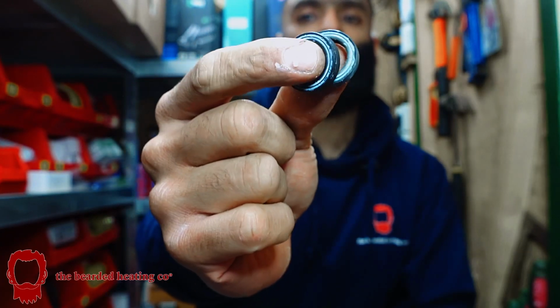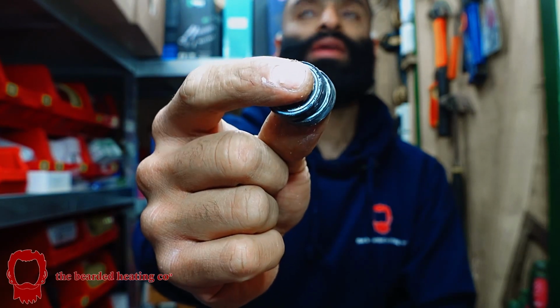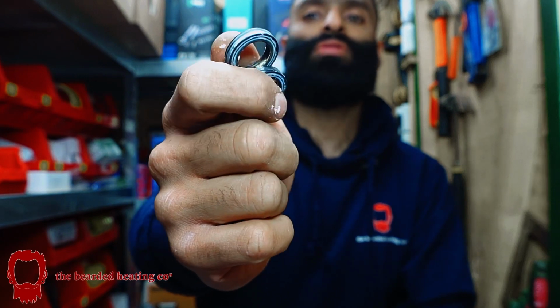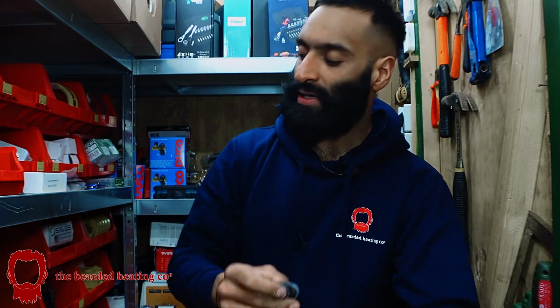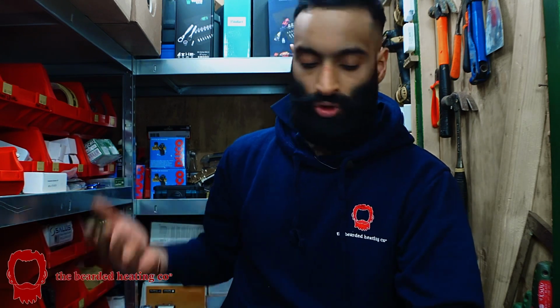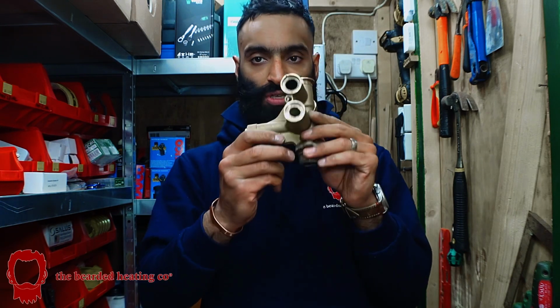So always replace these rings when you're working on a plate heat exchanger, because they leak. They get a bit hard, they get brittle, they get soft, they get flatter, they lose their shape and their integrity, and they will cause you leaks. So whenever you change a plate heat exchanger, always change them.